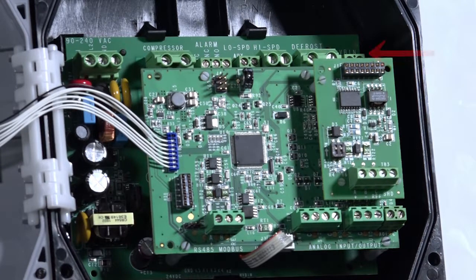specific temperature is achieved. The A525 also has a high voltage binary input which can receive a signal from a bimetallic switch that is commonly used in evaporator systems for defrost termination. If wired to the high voltage binary input, when the bimetallic switch reaches the defrost termination temperature, the defrost cycle will stop. The A525 has 2 universal inputs which can receive either a binary input signal or an analog signal. These can be used to receive a signal from a door switch, a refrigeration leak detector, man-in-room, or just about any other signaling device. When a signal is received, the control can be set up to perform a specific action, such as shutting down the system or sounding an alarm.